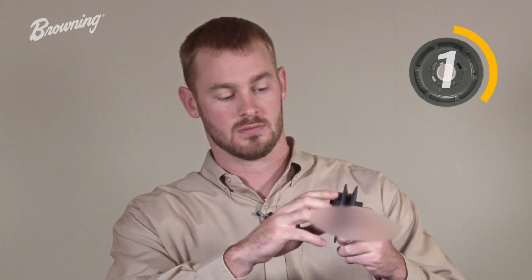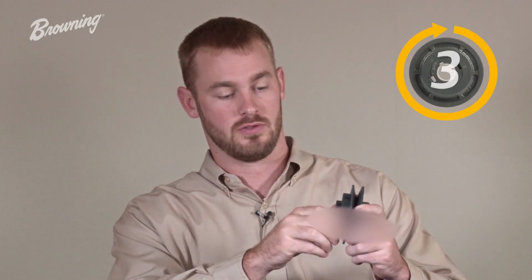For applications utilizing variable pitch sheaves, the current pitch diameter will have to be calculated before the speed can be calculated. To do this, we will need some additional information. For example, let's assume this sheave was just removed from the motor shaft. I loosen the set screw above the keyway and count how many revolutions it takes to close it. 1, 2, 3 and a half. 3.5 turns open. Now I list that information in the application data sheet.